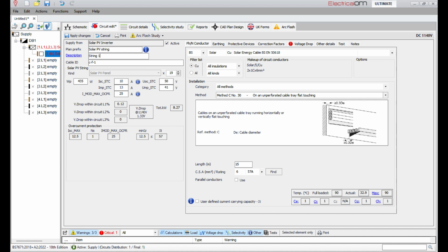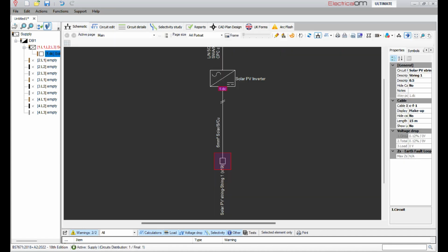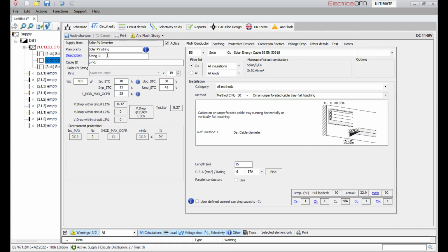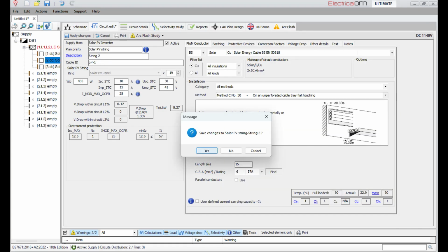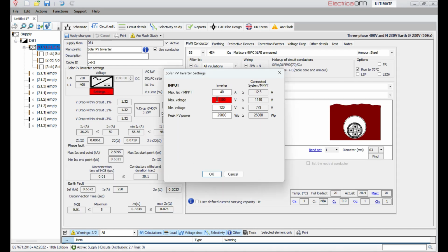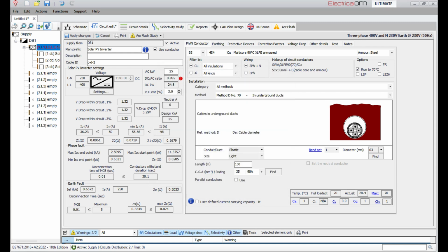You see, again, looking at the volt drop figure now, if you see over on the left-hand side before we exited that screen, it did adjust. But I'm just pasting similar in now. So we've got our three strings generating into our three-phase inverter. And you can see the volt drop within those circuits has moved. We have got a maximum voltage rating on the inverter set to 1,000 volts. So I'm going to bump that up to 1,500 to cover us off there.